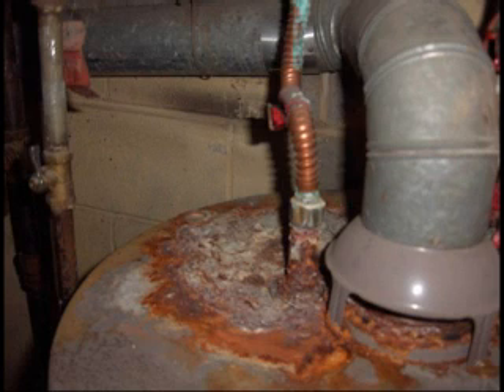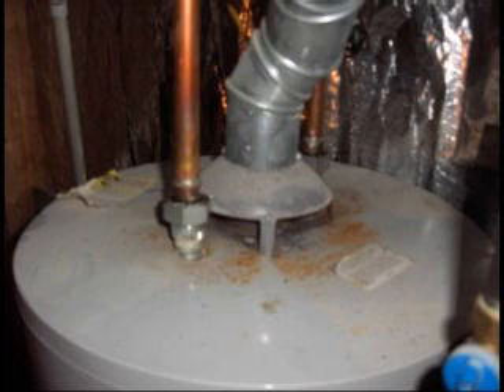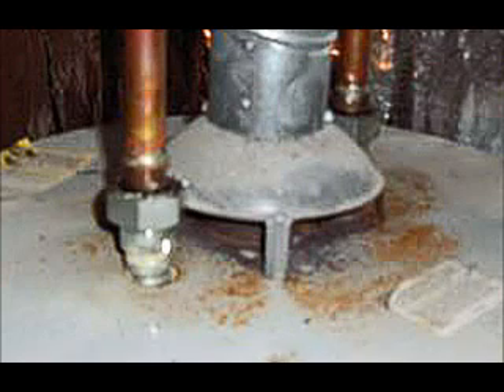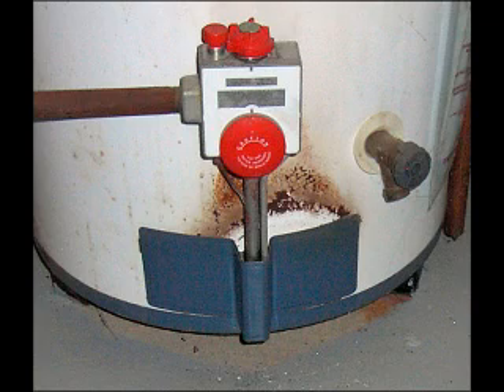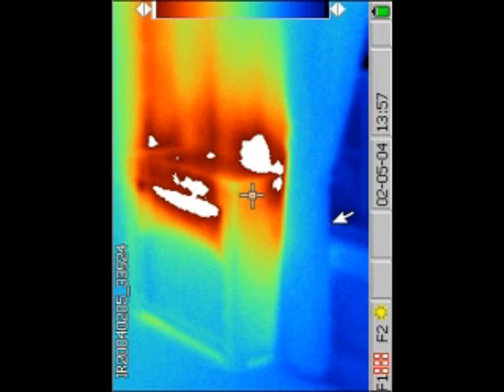One of the easiest ways to know if you have a problem is just go downstairs to your water heater. If the top of the water heater is rusted, a lot of plumbers say it's a plumbing leak or condensation. Well, if it's rusted, it's spilling at the water heater. In other words, the draft is too low. If the rust stain is down at the burner, the lower section, then many times it's because the draft is too high.